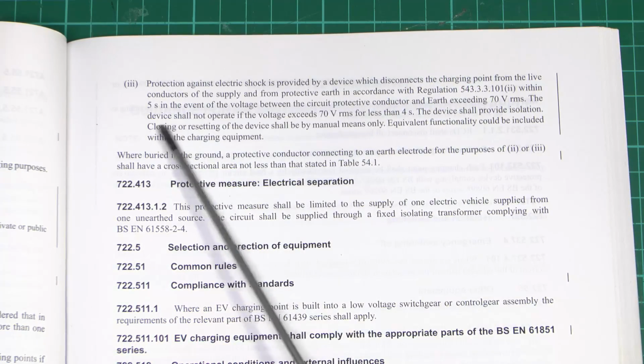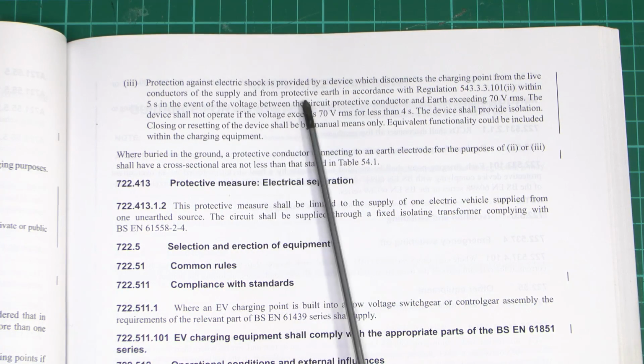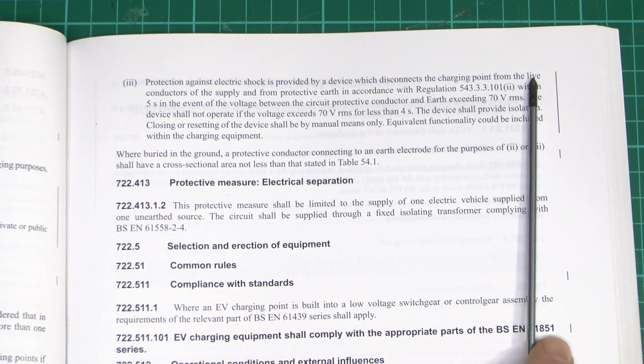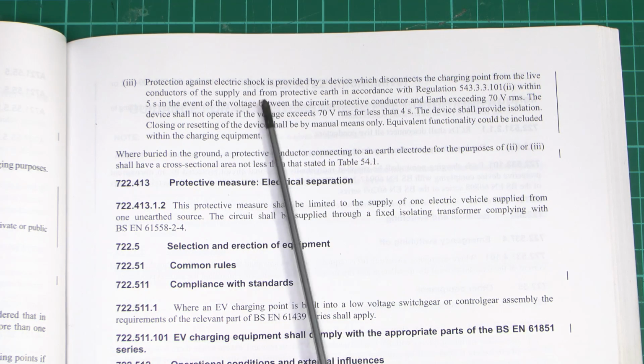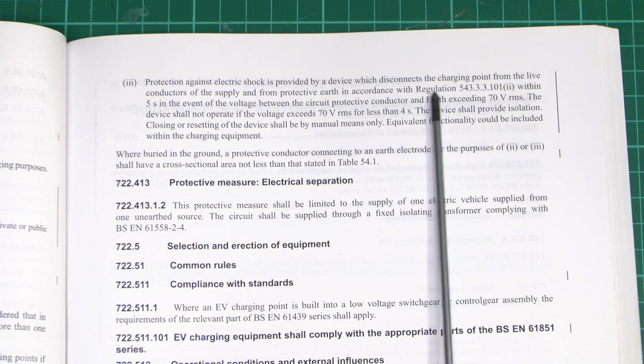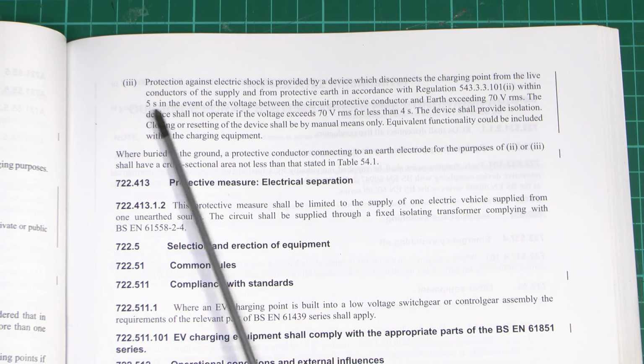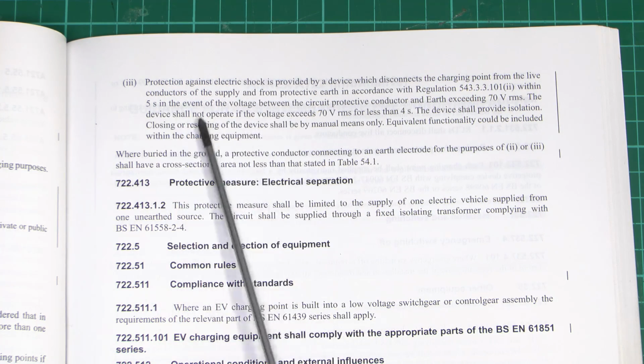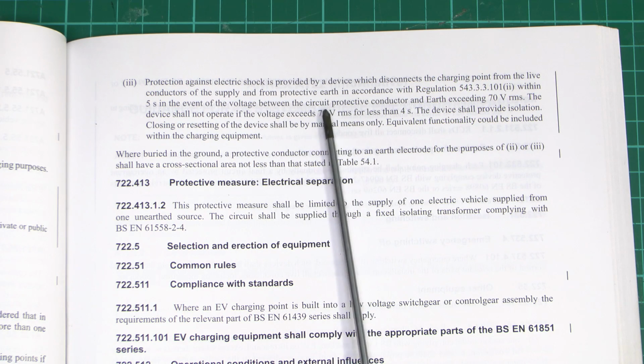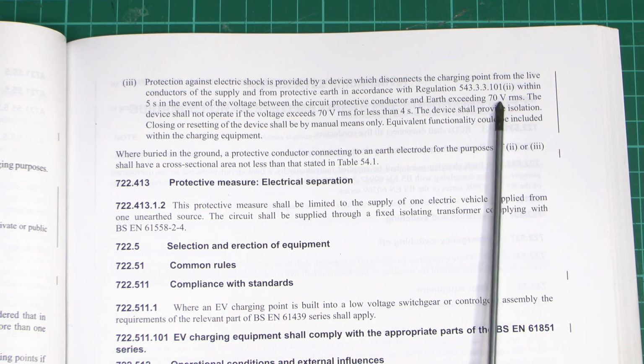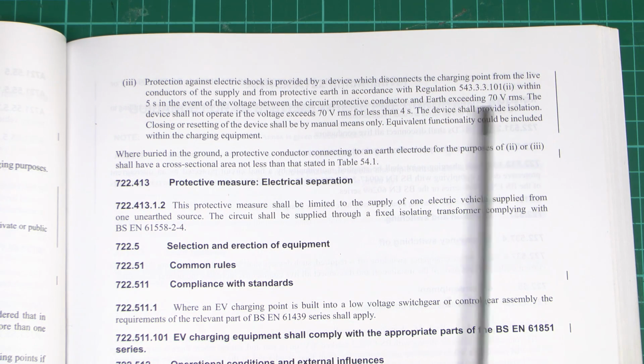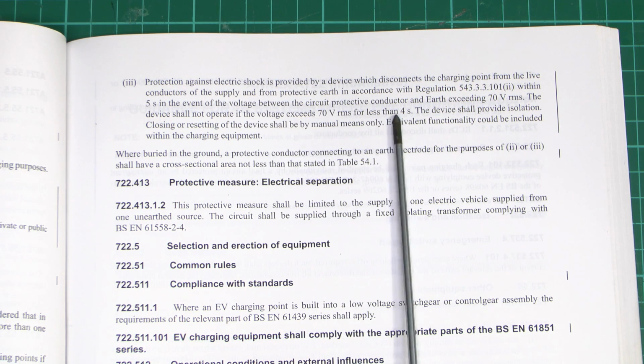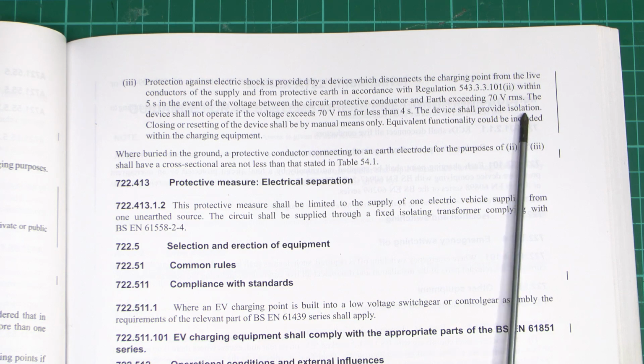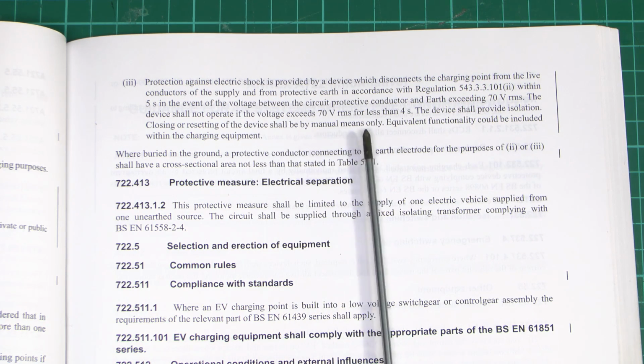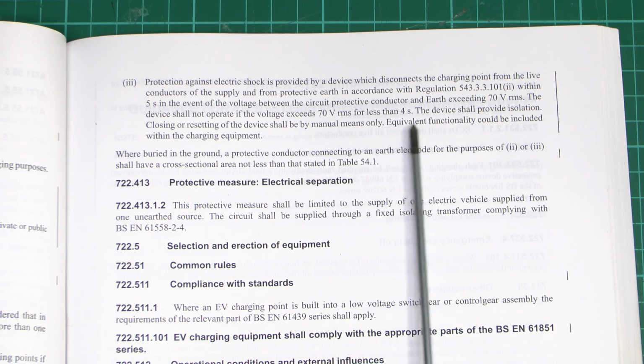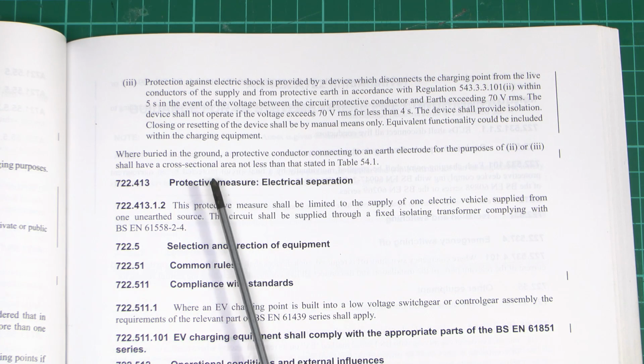And the third one, which in theory you could use, is that protection against electric shock is provided by a device which disconnects the charging point from the live conductor of the supply and from the protective earth in accordance with this regulation. It disconnects within 5 seconds in the event the voltage between the circuit protective conductor and earth exceeds this 70 volts RMS again. And it should not operate if it exceeds 70 volts for less than 4 seconds. The device shall provide isolation, and closing or resetting is by manual means only. Equivalent functionality could be included within the charging equipment.